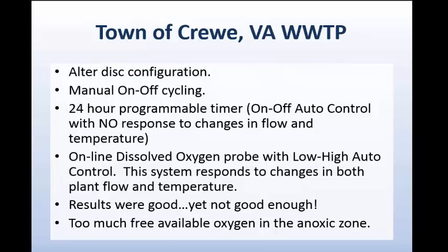So after altering our disc configuration, we tried to see what kind of results we could get if we manually cycled our rotors or those discs off and on. And in doing that, this plant is not staffed 24 hours a day. We could only do the manual on and off cycling while we were here, so that didn't give us a real picture, but it did show that we could get some success. And in fact, by altering that on and off cycle, we could get some successful results.